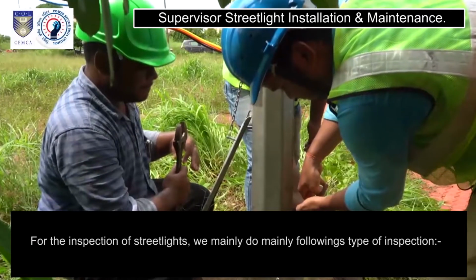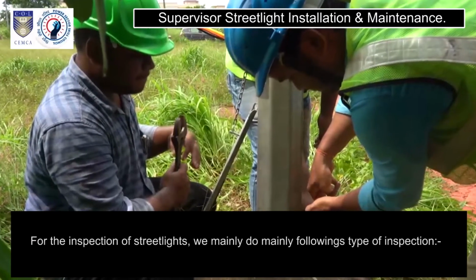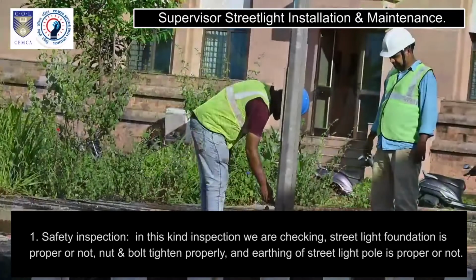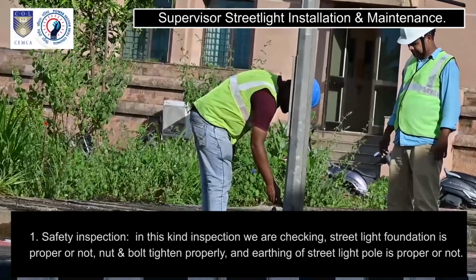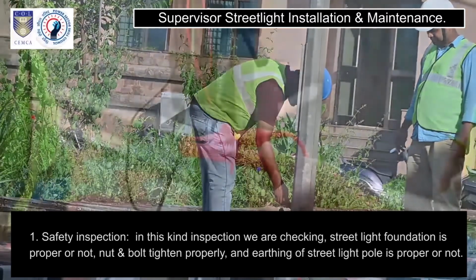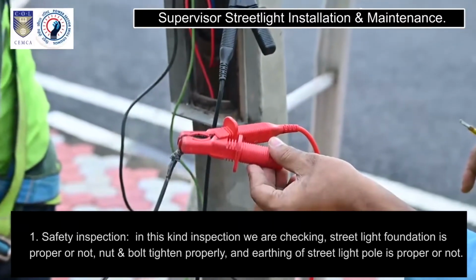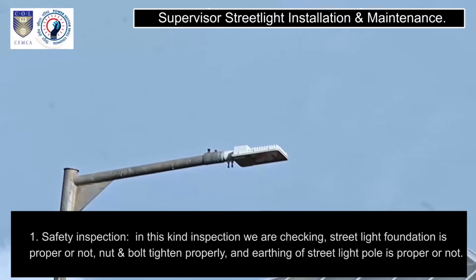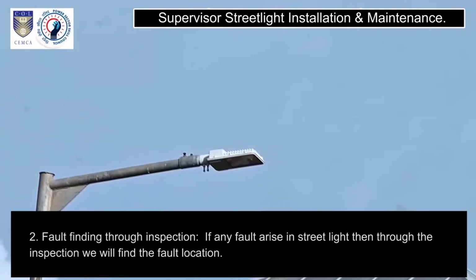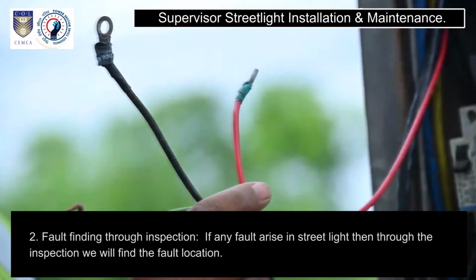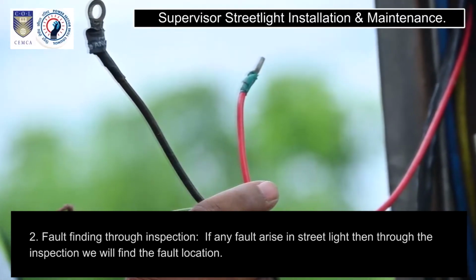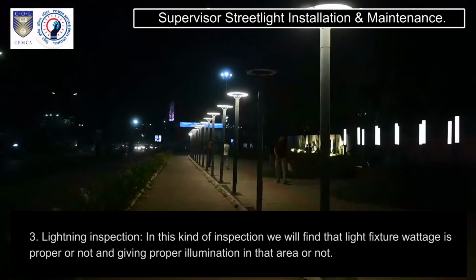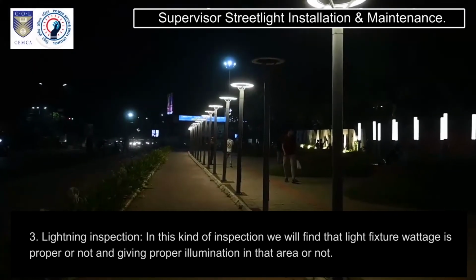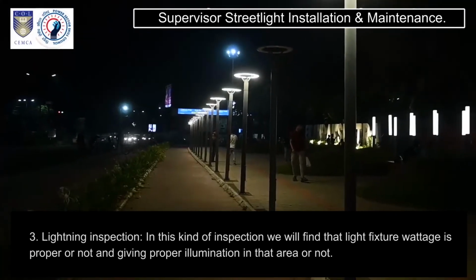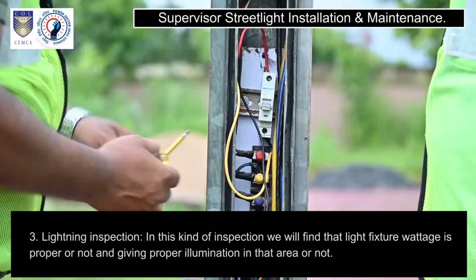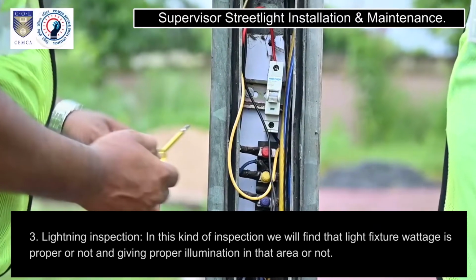For the inspection of streetlights, we mainly do the following types of inspection. 1. Safety inspection. In this kind of inspection, we are checking whether the streetlight foundation is proper or not, nuts and bolts are tightened properly, and earthing of the streetlight pole is proper or not. 2. Fault finding through inspection. If any fault arises in a streetlight, then through the inspection, we will find the fault location. 3. Lighting inspection. In this kind of inspection, we will find whether the light fixture wattage is proper or not and giving proper illumination in that area or not.